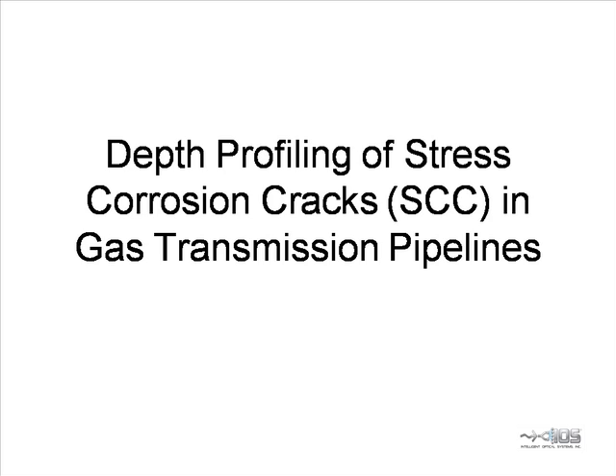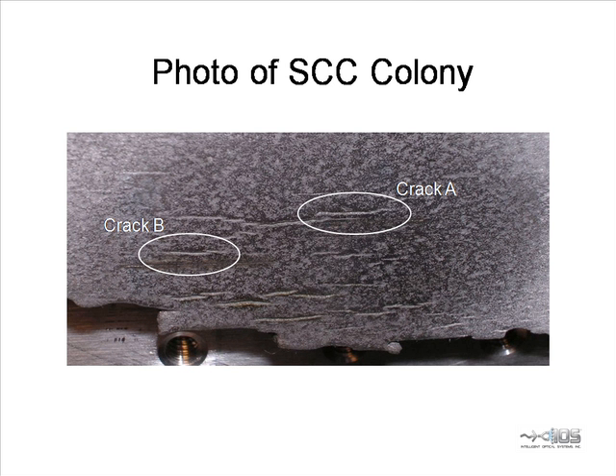The second application is depth profiling of stress corrosion cracks in gas transmission pipelines. We show a photo of a colony of stress corrosion cracks, which appear close together with varying lengths. The crack spacing is too small to allow the use of conventional transducers for isolating a single crack. Laser ultrasonics has the benefit of a very small spot size to interrogate a single crack at a time.